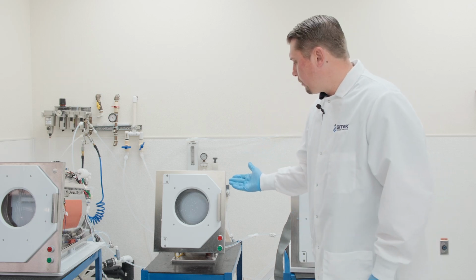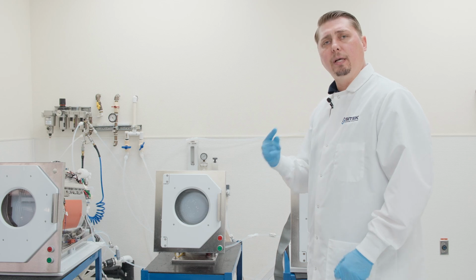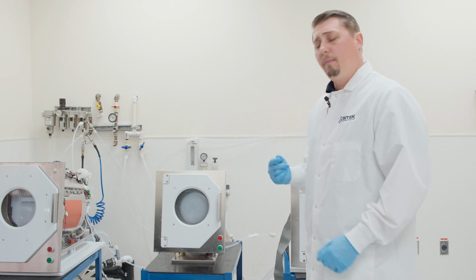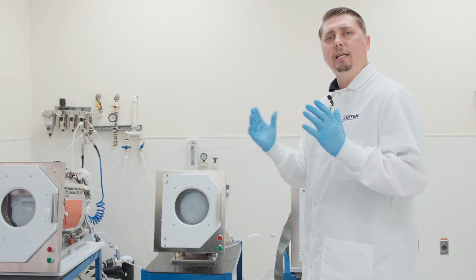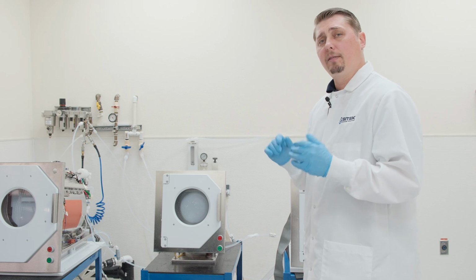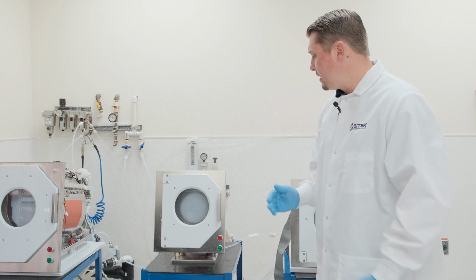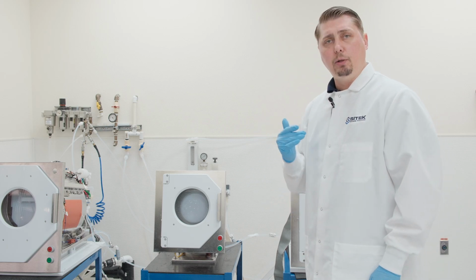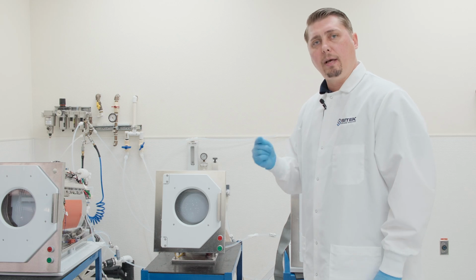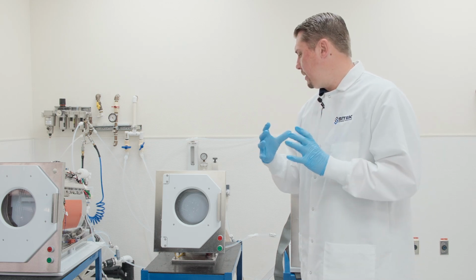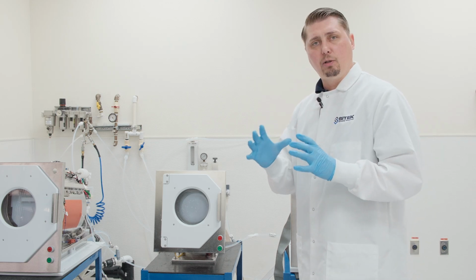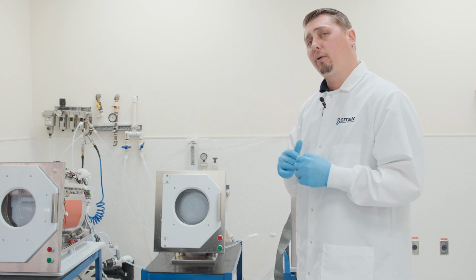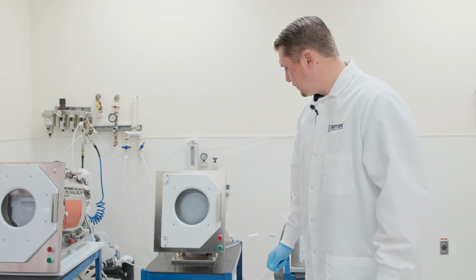Now it'll go into heat 1, where the RPM will speed up dramatically, allowing the force to fling any large water particles off the substrates. After this, it'll go into dry 2, where the RPM will slow down and the heating elements will kick on, drying any particles still on the substrates.